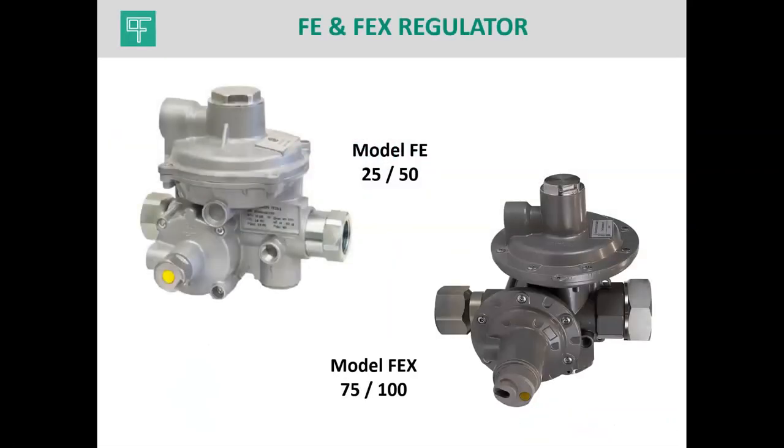The FE family of overpressure shutoff, also known as OPSO or OPCO pressure regulators, was first introduced to the European market over 30 years ago. At that time, there was an initiative to reduce emissions of greenhouse gases, and the use of full capacity relief regulators was eradicated. In this lineup of service regulators, there are two distinct formats, FE and FEX models, with flow rate capacities ranging from 875 cubic feet an hour up to 3,500 cubic feet an hour.